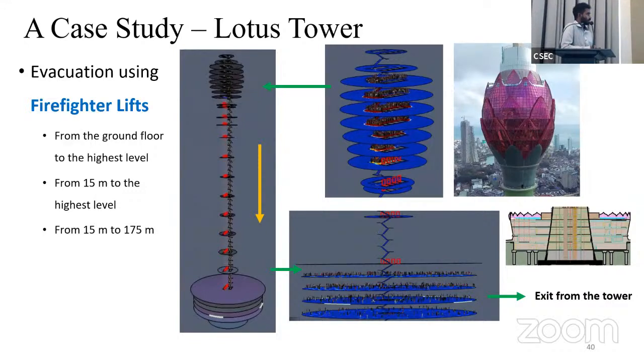So this evacuation time will govern the required fire protections for the structures, and this kind of model we can use to do performance-based designs. Based on the performance, we can decide the required fire safety. Here, we can define the main exit from the building. Then all the people follow the routes towards this main exit.